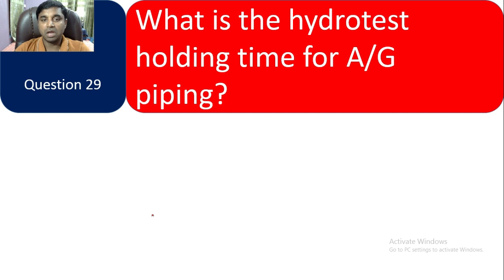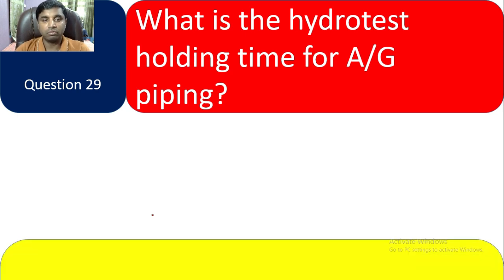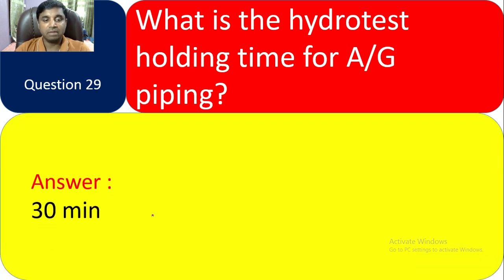Question 29: What is the hydro test holding time for above-ground piping? The holding time is 30 minutes for above-ground piping.